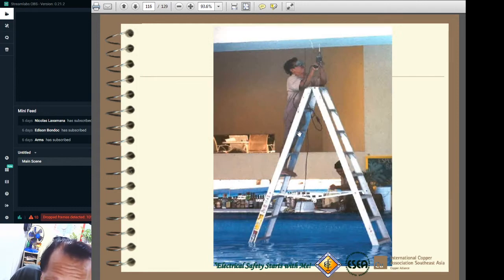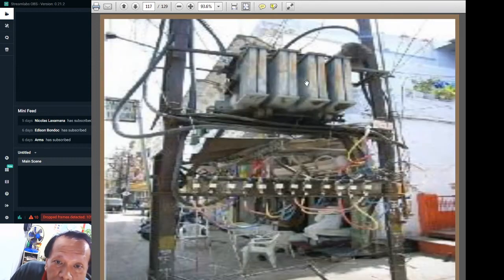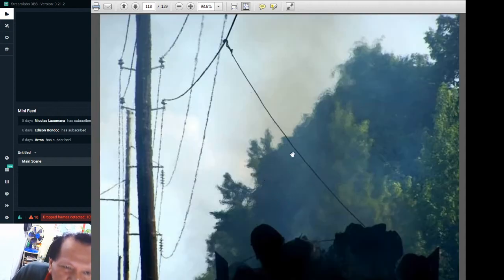And this should be avoided, because doing electrical works like this, he might fall and he might get electrocuted when he falls from the pole. So it's not the correct way of doing the job. There's a possibility that he might fall. Okay, and here is a transformer installation which is very low, and also the meters are very low, and could be touched by people passing through the street. It's so dangerous.